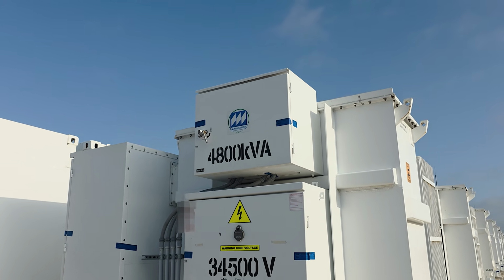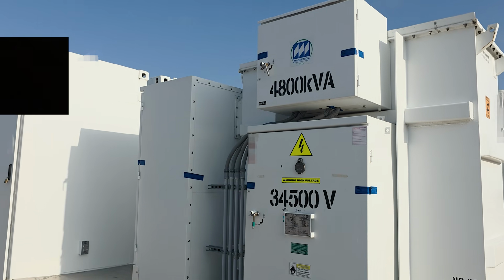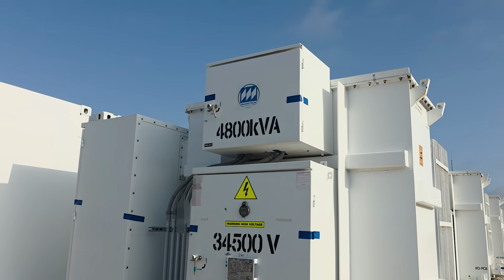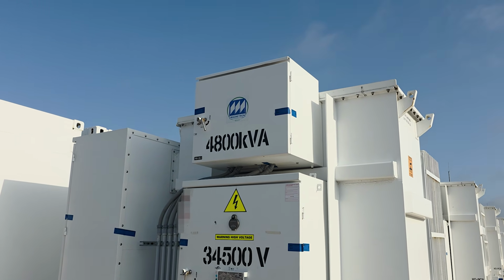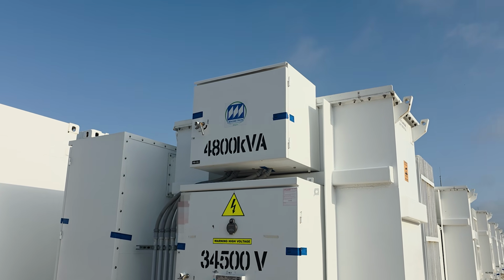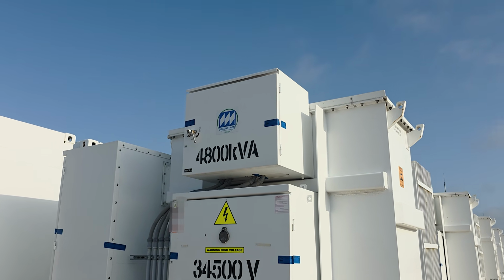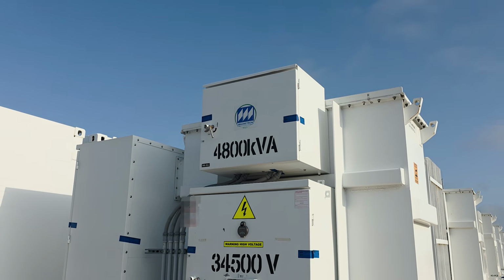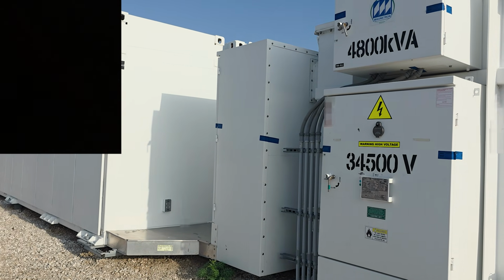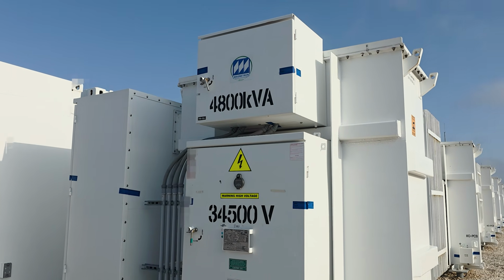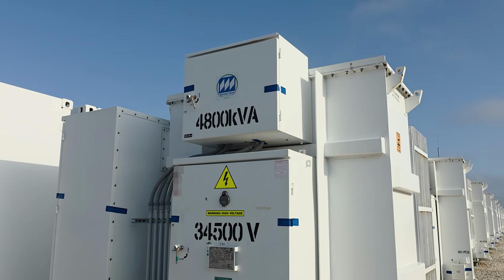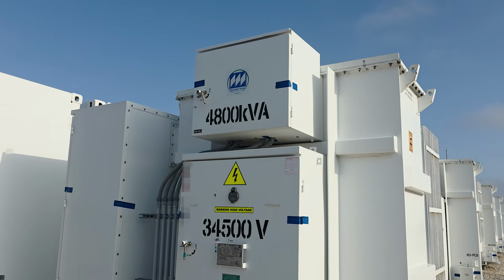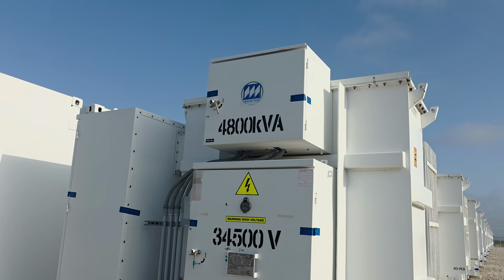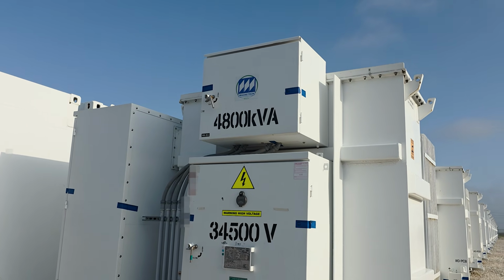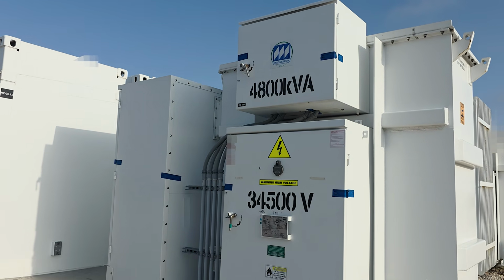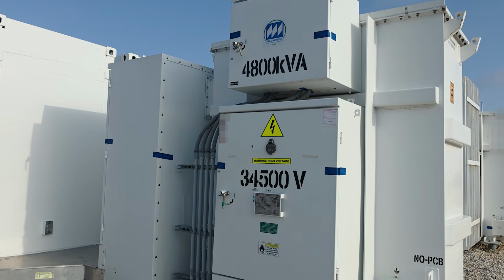There are also emergency circuits coming from the batteries that will talk to the relay here, and then that relay will again send that signal through to the substation to say, hey, I have a problem with one of my batteries, open me. And so that circuit will open, which will de-energize the inverter. But you notice I did not say de-energize the batteries. You cannot de-energize batteries. There is stored power there that has to be discharged somehow, and that's kind of different. So what this will do is turn off the inverter. So it'll at least isolate anything that's going on from that battery back to the substation.